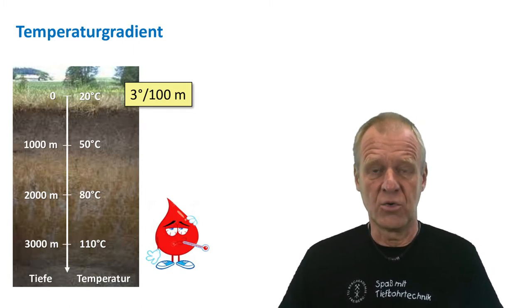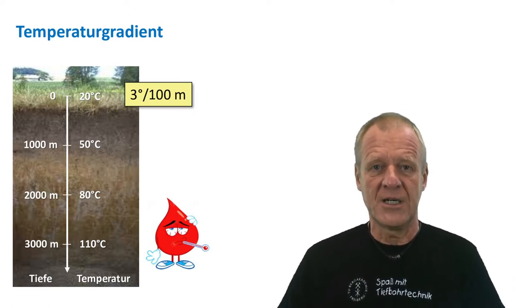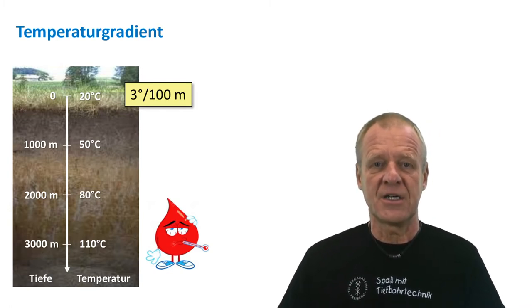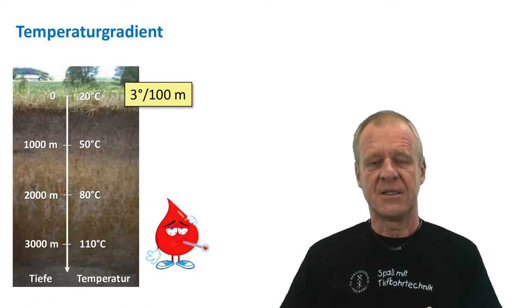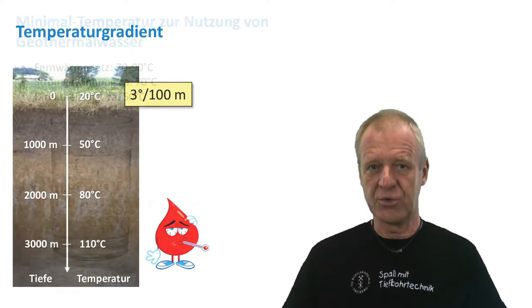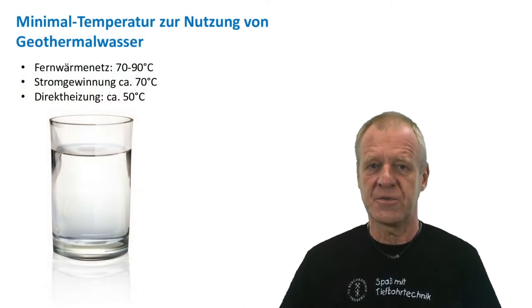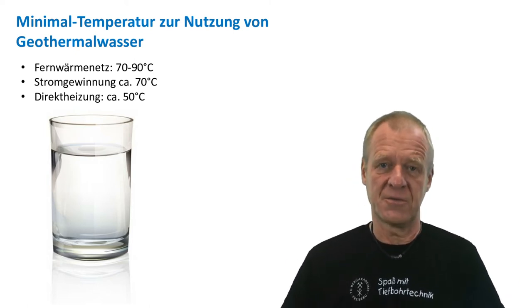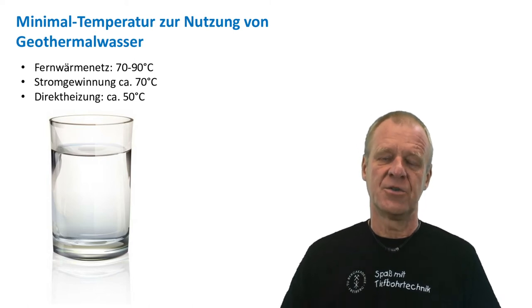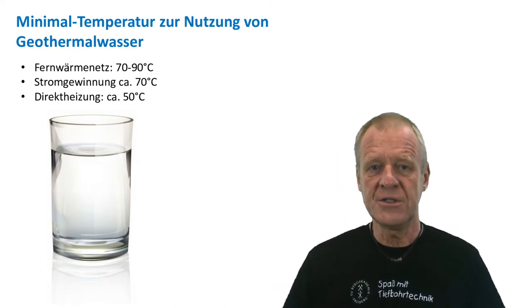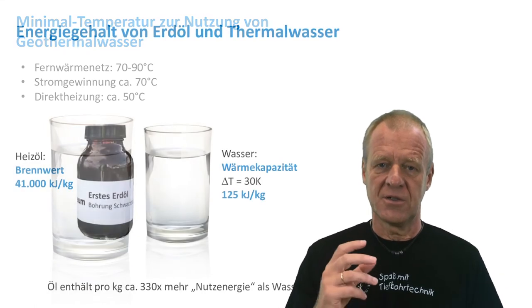But if we assume that there was free moving hot water at the target depth, then there is a second challenge. In our power plant at the surface, we can only use the heat which we withdraw from the water. We have to consider that technical processes require certain temperatures. For example, a district heating system — if the water has a temperature of less than 60 or 70 degrees centigrade, the customers will not be able to heat their houses properly. So if our borehole produces hot water at 100 degrees centigrade, we can only let it cool down to about 70 degrees centigrade. After that, the heat content of the water is no longer technically usable. This means we can only use the heat if we cool the water down by 30 degrees — and that is not a lot.